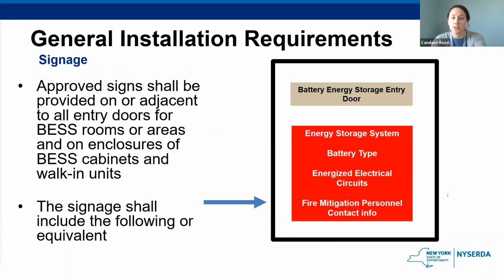Here we have the signage that is required for each battery energy storage system. It should be provided on all entry doors to storage system rooms, to walk-in units located outdoors, on rooftops, or in open parking garages, and on the enclosures of the cabinets. This is necessary to let people know that there are batteries in the location, what type of batteries, that it is energized, and emergency contact information in case of an incident. There may be additional signage that is required from the National Electric Code, but this is just specifically what is required in the fire code.